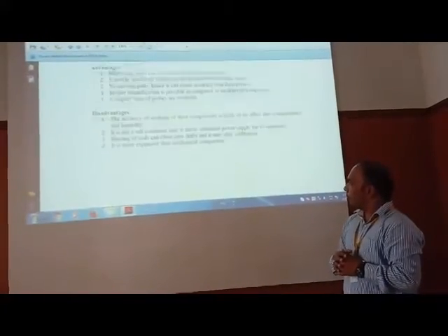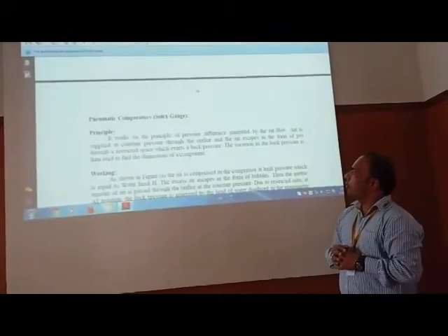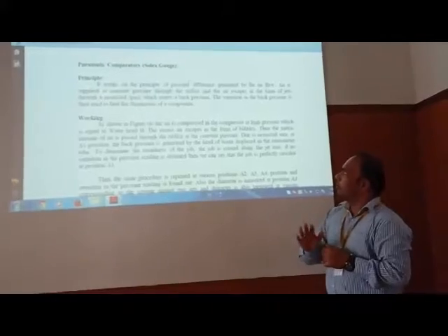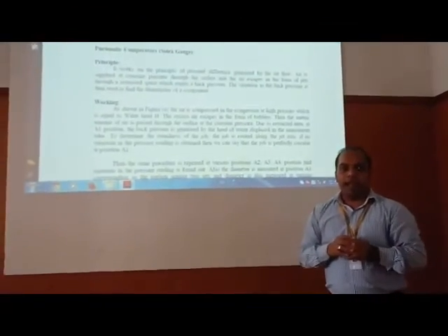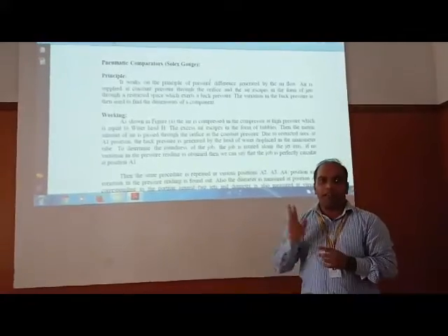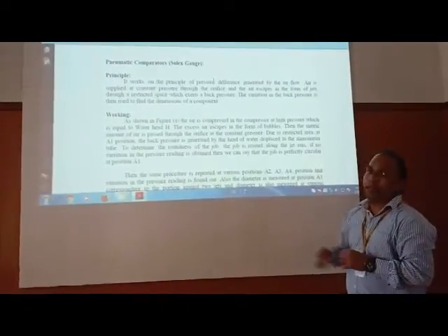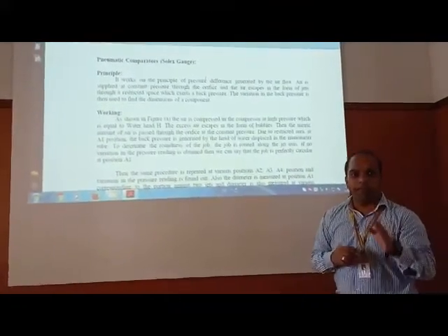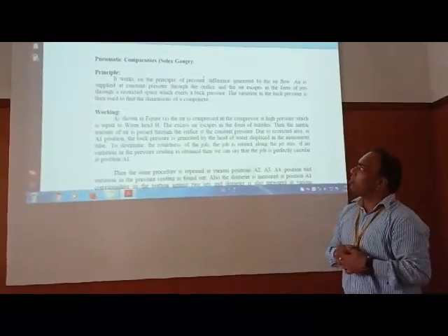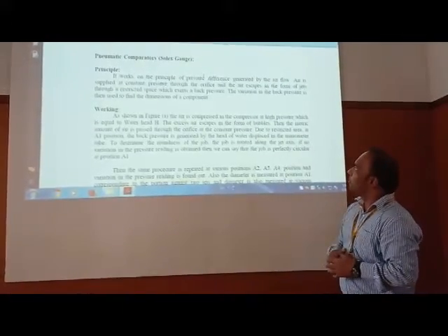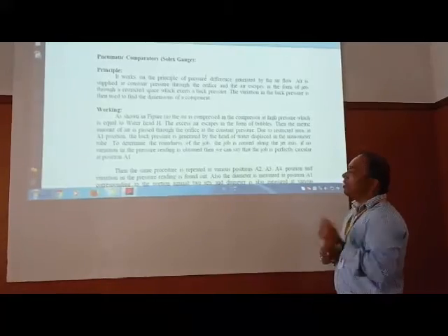Next, the pneumatic comparator. As promised, this is the pneumatic comparator and we are going to see the working of it. Let us first note down the basic principle behind its working. It works on the principle of pressure difference generated by airflow.